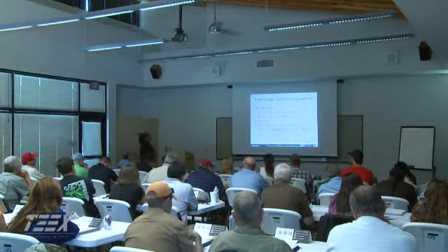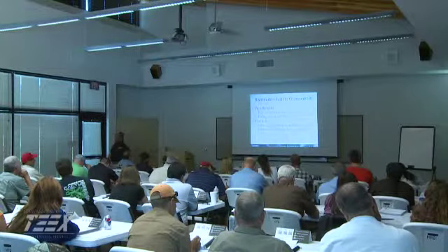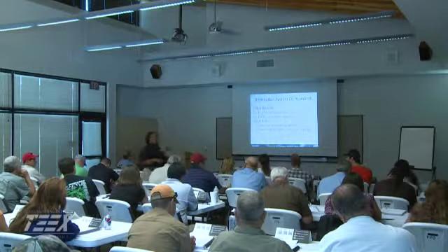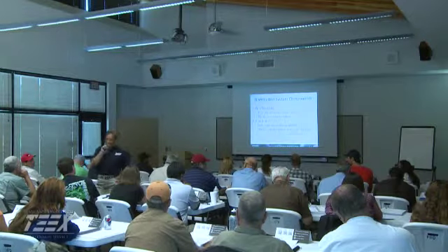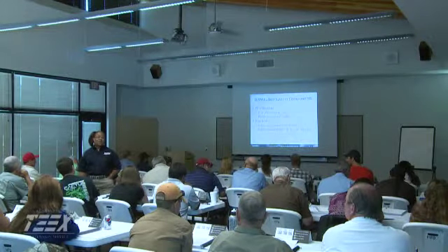Maximum lead content, as far as your fitting and solder and flux, some people like to say, 8%, no more than 8%, okay? 2% in your flux and solder. That changes as of January, so what are you all going to do? Do you know the new requirements as of January 2014? What lead content? 0. They give you a little. They don't take it all the way to 0, but 0.25, that's so close to 0, might as well be 0. So have you started thinking about what you're going to do?